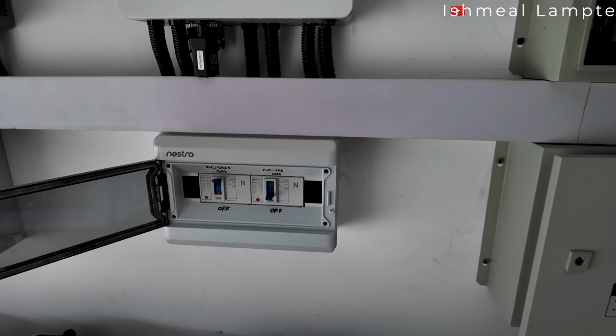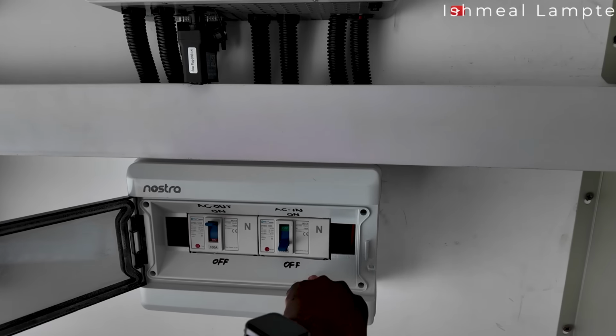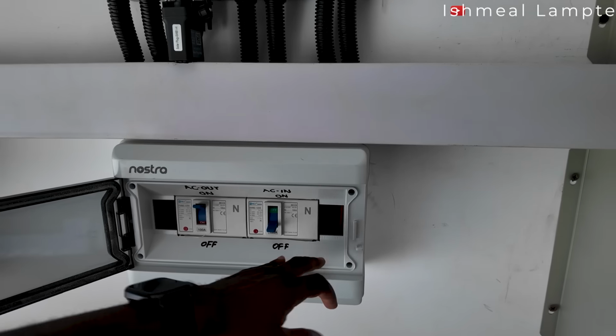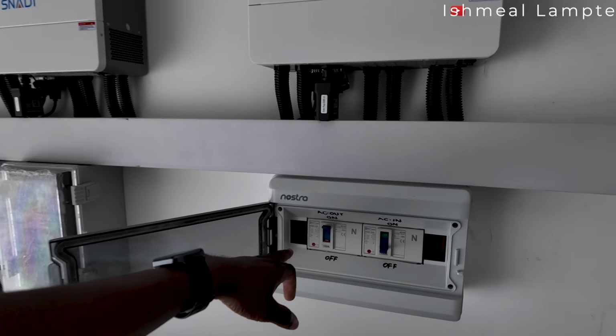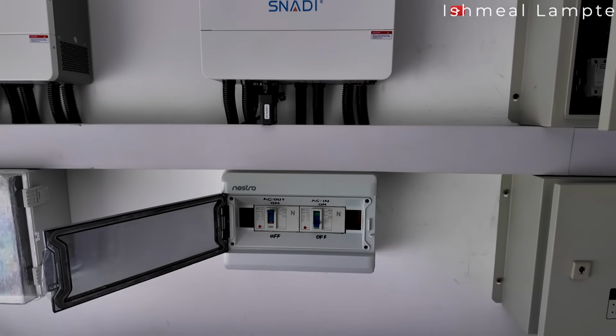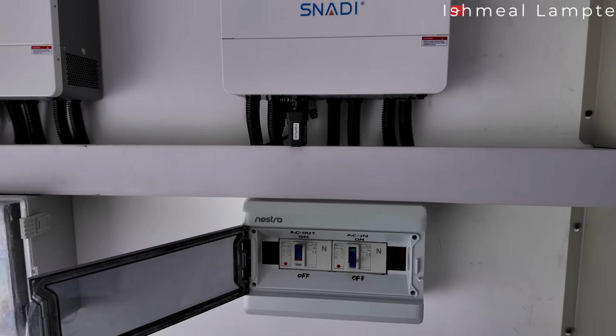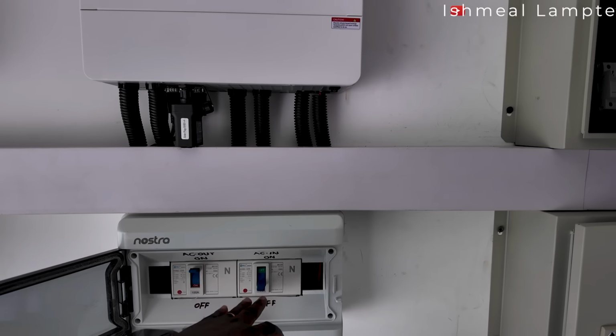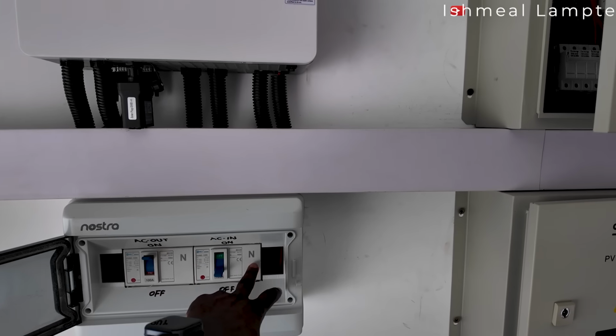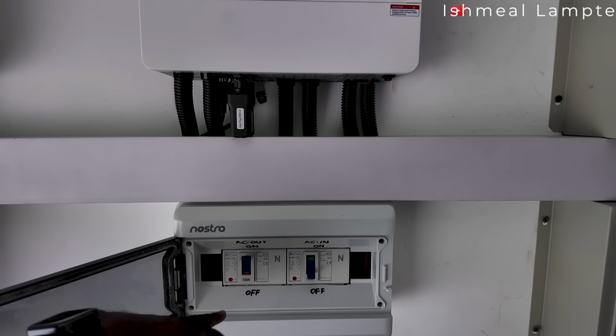So that is the power coming from the grid. It comes into this MCCB before it goes into the inverters. These are introduced to be able to isolate the system. In case you want to turn off the AC input, you're able to do that with this MCCB. The same for the AC output, you're able to do that with the MCCB over there.